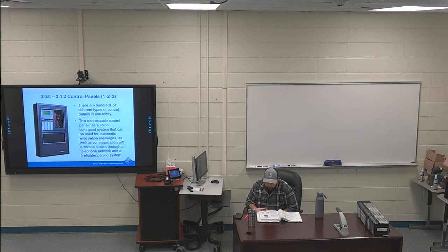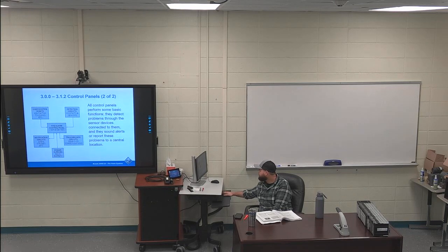So you can see figure 29 shows the fire alarm control panel inputs and outputs. So you can see the inputs would be control points, which would be the key switch touchpad, which is right there on the board. And then you have your detection circuits, your contactors and your sensors, smoke alarms, and then your power supply, which is your main battery going in. And then outputting, you can have your notification circuits, so your outputs with your sirens or your horns or your strobes. And then you can also have your transmission circuits, which tells the fire department to come. So most of them all kind of work the same but different. Going on to page 24, 310.